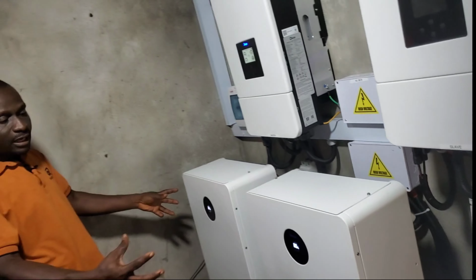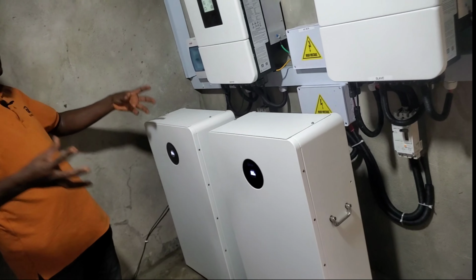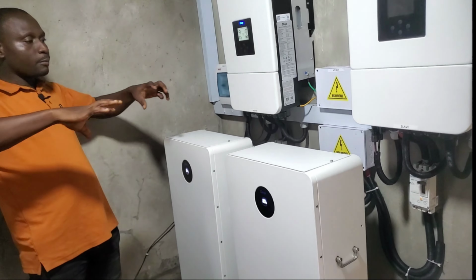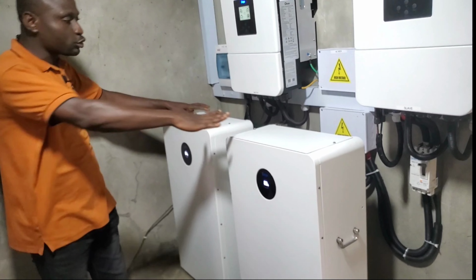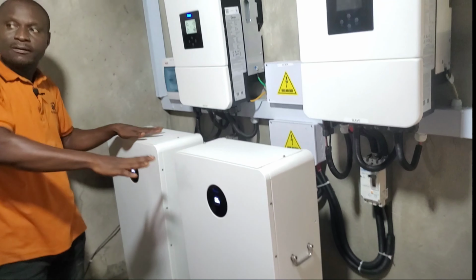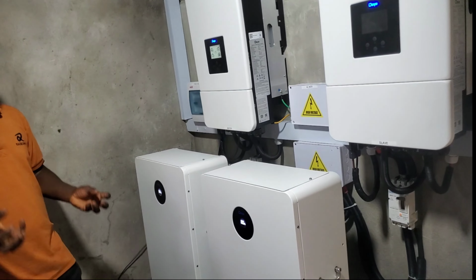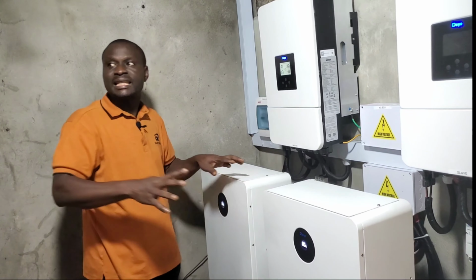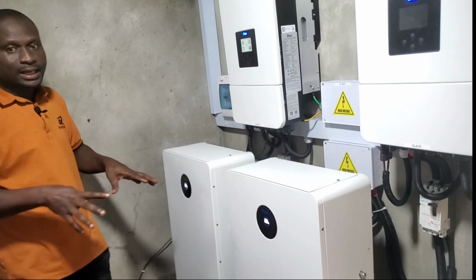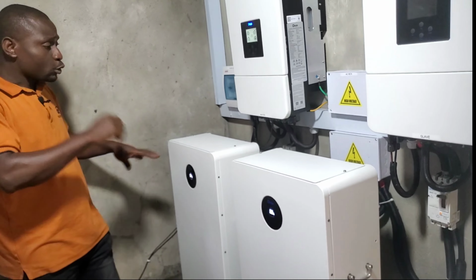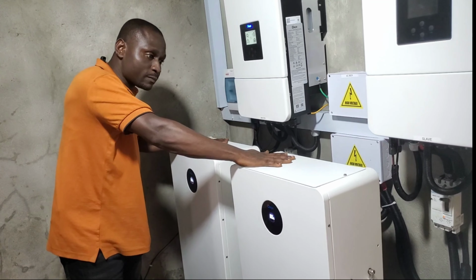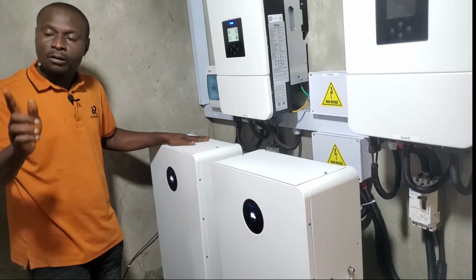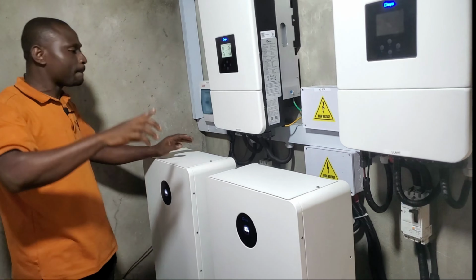Now we join them together because we need high capacity. We need big or large capacity. So we join them together. Here we connect them for parallel because we want make the capacity dey high. So the total wey dey here now na 32 kilowatt hour. That is 16 plus 16. So wetin dey stored for this battery na still direct current wey be DC wey I don first tell una.